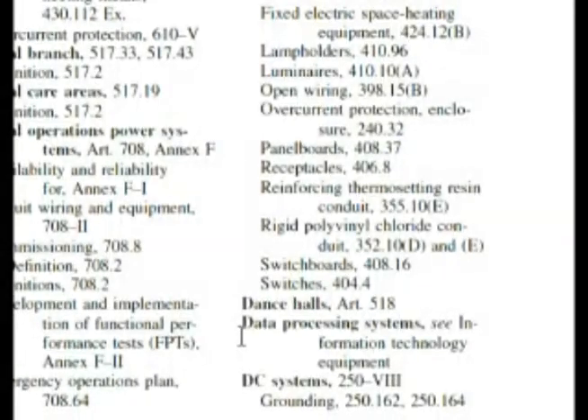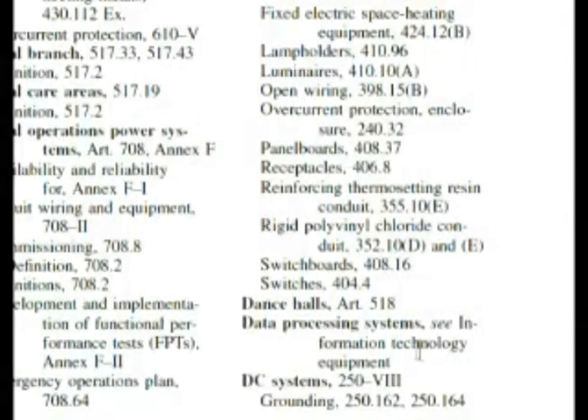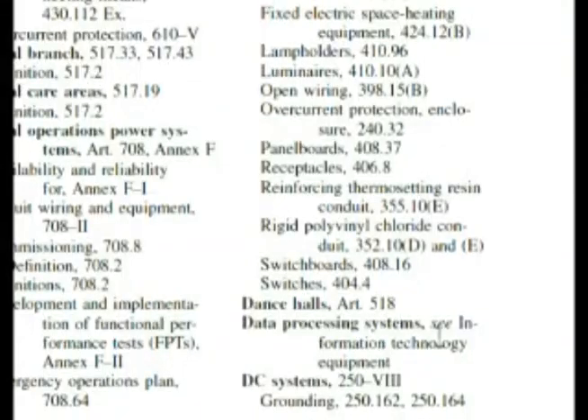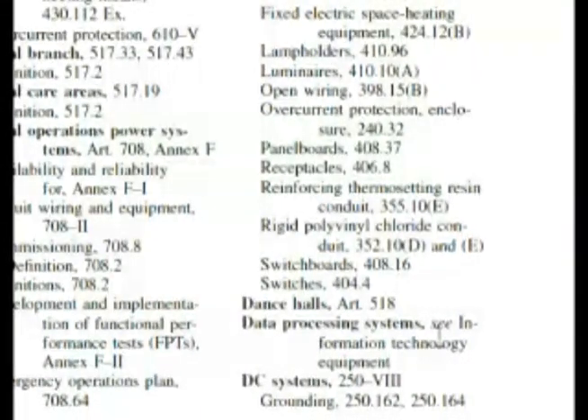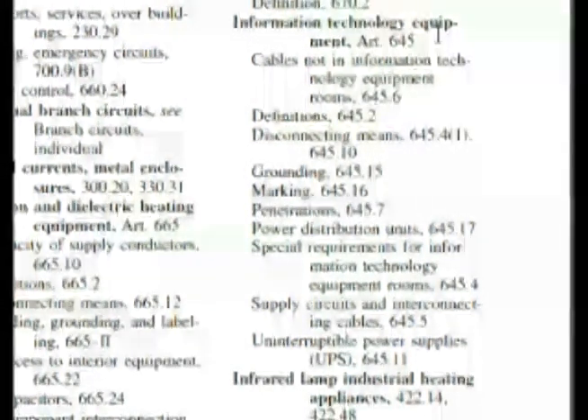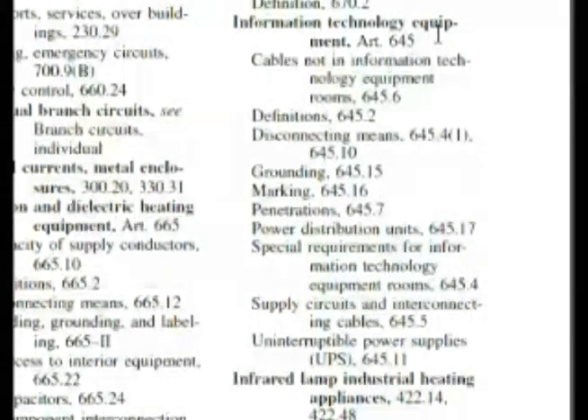Here we are at the index of the code book — data processing systems — and it's telling us to see information technology equipment. So let's look under information technology equipment. We're at the index: information technology equipment, and it says Article 645. So again, if you knew that, you would know that data processing would be listed under that.